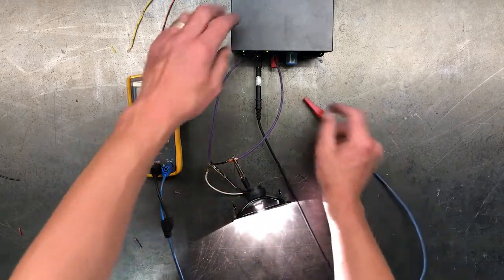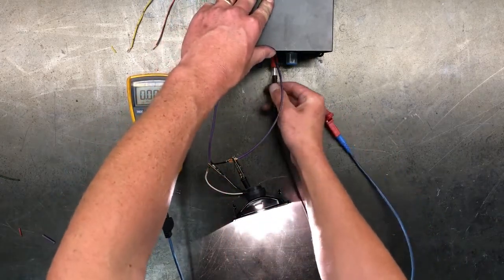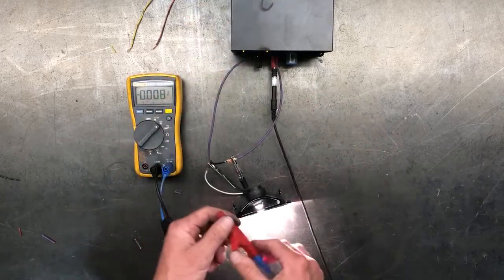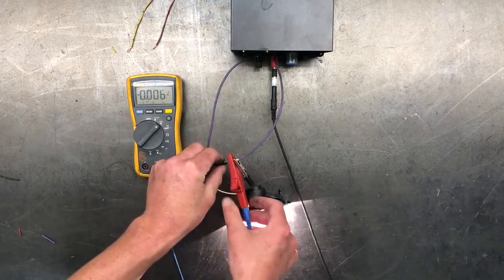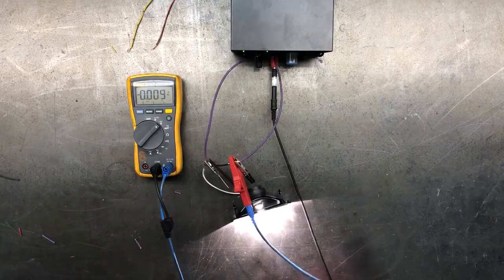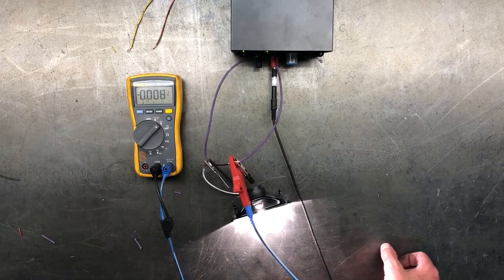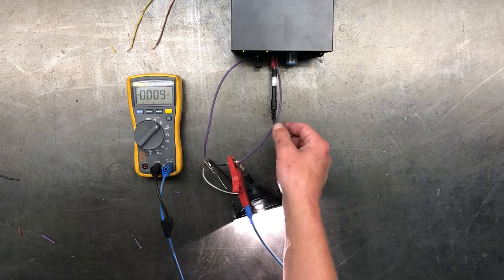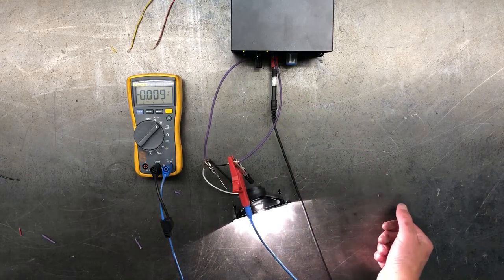Let's go ahead and check our positive wire. Positive wire is all the way down to 8 millivolts. So this wire is great. That means we must have a really good connection on both ends. We're not losing anything in the connections. So that's another thing to be aware of.